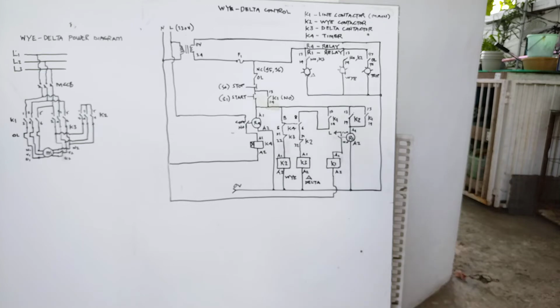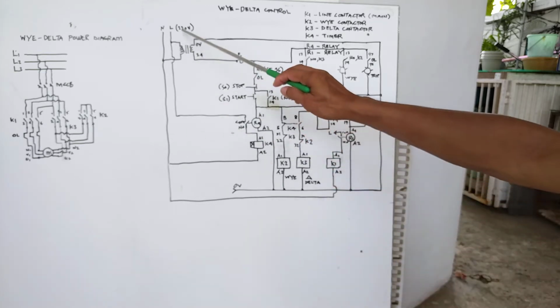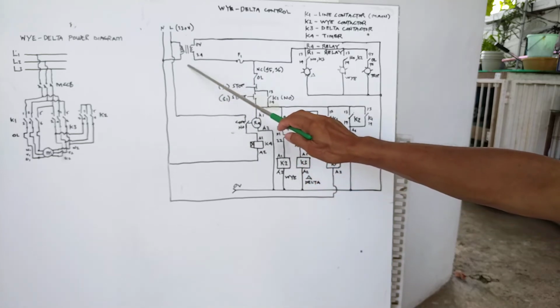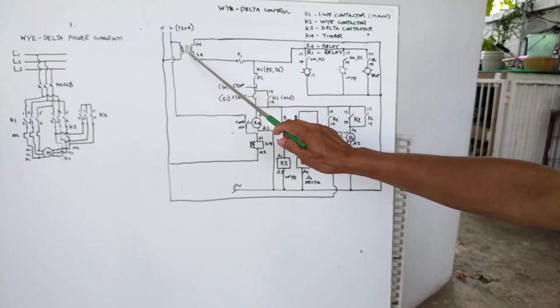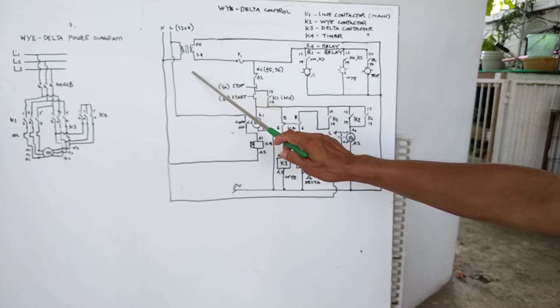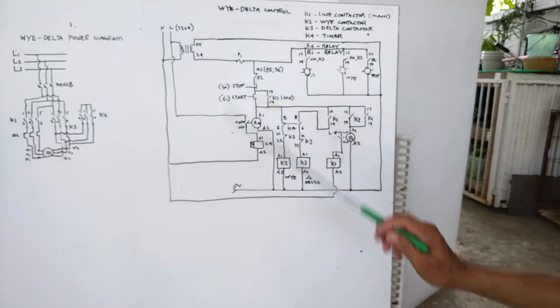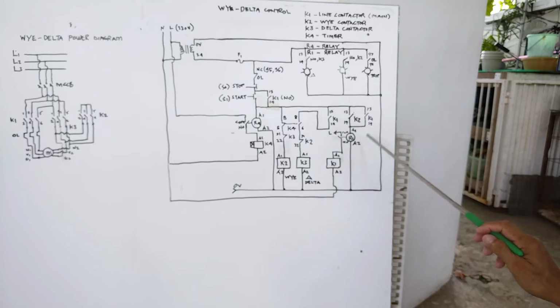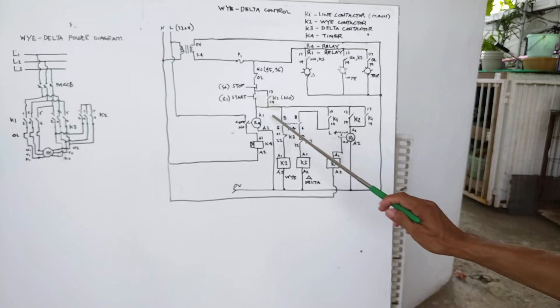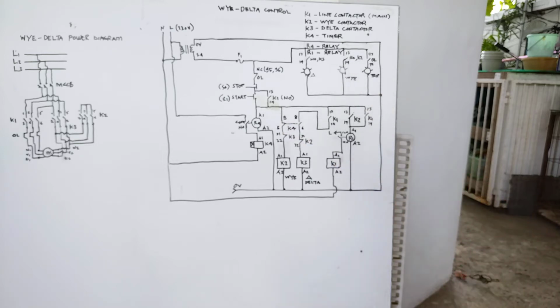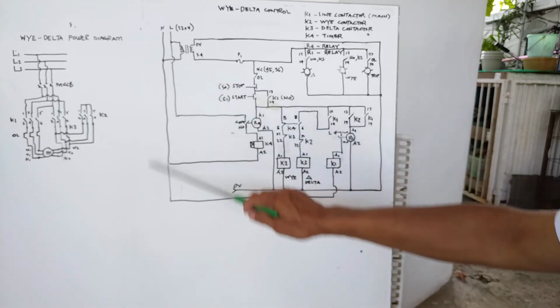Now actually my control power here is a combination of 220 and 24 volts. As you can see, I have a control transformer here, a 220 to 24 volts step down transformer. Why? Because I have a relay and indication lamp which are 24 volts, and two contactors, the delta and Y, whose coils are 24 volts. Now my timer's coil is 220, and also the coil of this K1 contactor is 220. As you can see here, this one is connected to the neutral line.